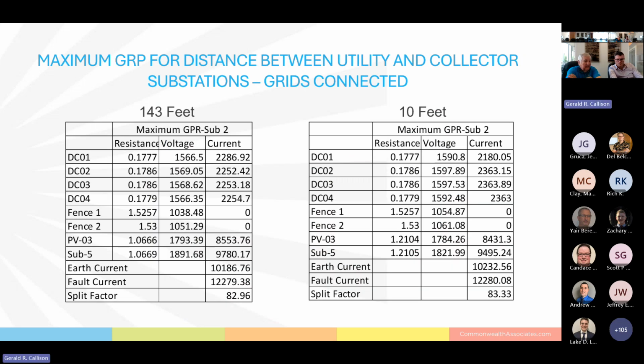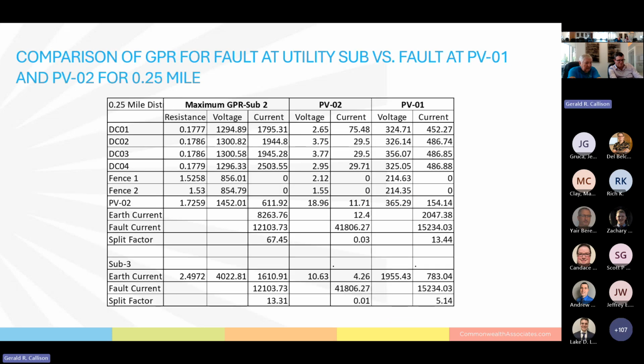So what happens when we look at the results when these ground grids are tied together and the distances are much closer together? Well, when it was a quarter mile apart, these voltages were approximately 1300 volts, and these were a little closer to 1000. And so the closer you get them together, you can see that the voltages actually do go up some. And the other thing that changes is the split factor between those. The split factor on the other one was lower than that. I can look at that. The split factors are only like 13% here. But when you tie the ground grids all together, then that definitely changes the split factor.